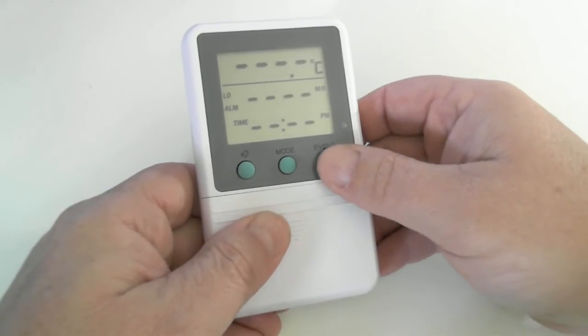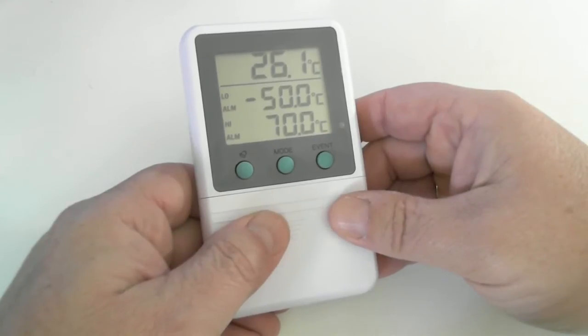If we press the event for this, this would show the low alarm time and date stamp, which we have not had an event so there is no data. Pressing again would give us the high alarm data. Press event again and we are back into the main alarm display screen.